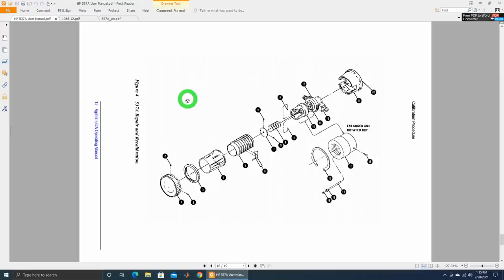So here's the exploded view of this frequency meter. So it's a purely passive device and you can see the different sections here. Here are the coaxial connectors going in and this is where all the magic happens. This is where the cavity is. The rest of it are basically supporting components and measurements and adjusting and keeping track of where the size of the cavity is. So there is a worm screw of some kind that is moving in and out of this cavity and that can give you very precise adjustment if it's done correctly and you can read where the location of that screw is and translate that to a frequency of the cavity resonance and that is exactly what's going on here.